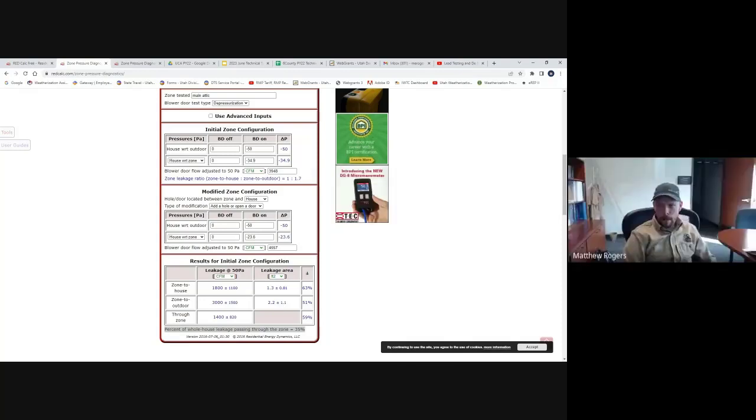Good. Yeah, only four. I need the blower door number with the house closed up and the zonal pressure into the zone you're testing. Then you open the door into the zone you're testing, get your blower door number again, and a zonal into that zone again. Those are the only four numbers I need.